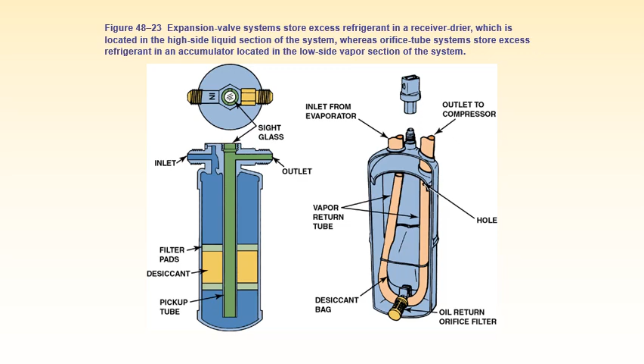Where it is used on the high side means at the outlet of the, we can say, condenser. Now this system is used in the orifice type at the low side, means at the outlet of the evaporator. So the inlet from the evaporator goes through these tubings. Here are the desiccant packs to take away the moisture, and this oil return is used. Any oil which is there in the system can return from this line. Any moisture which is present is taken by this desiccant bag. Here there is a hole. The hole is provided so that the water particles or moisture particles are absorbed, and only the refrigerant will go to the compressor.